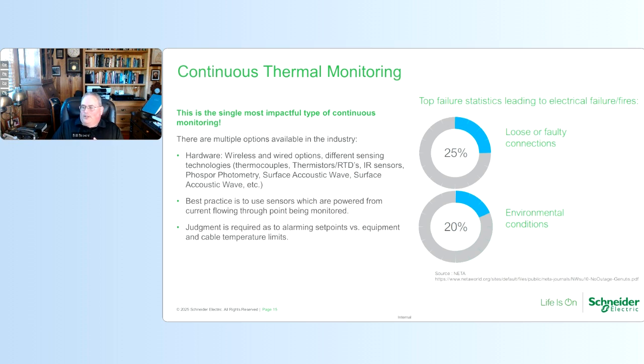There are multiple options for the technology used, much more than I have time to talk about here today in detail. Examples are thermocouples, thermistors, RTDs, IR sensors, phosphor photometry, and surface acoustic wave. A best practice for sensor technologies which require a source of power is to use sensors which are able to harvest energy from the current flowing through the location being monitored. Where humidity monitoring is an option, it's best to have this also. So, having exact temperature and humidity information on a continuous basis is empowering, but care has to be used in the setting of alarm set points so that they're realistic and they reflect potential encroachment upon equipment and cable temperature limits. And those limits are going to be different for different types of equipment and cabling.